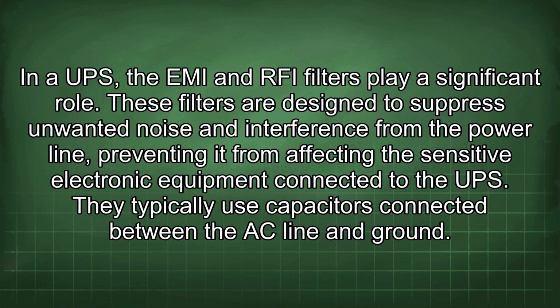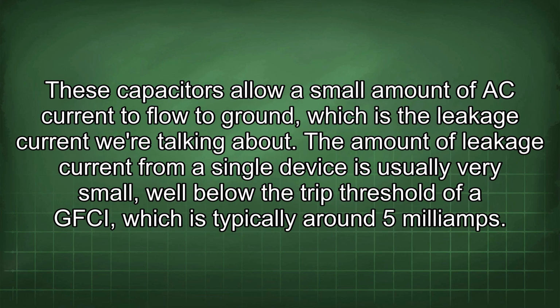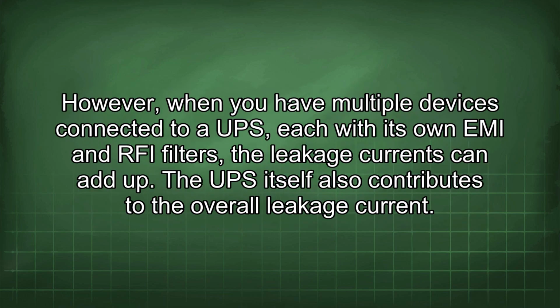They typically use capacitors connected between the AC line and ground. These capacitors allow a small amount of AC current to flow to ground, which is the leakage current we're talking about. The amount of leakage current from a single device is usually very small, well below the trip threshold of a GFCI, which is typically around 5 milliamps. However, when you have multiple devices connected to a UPS, each with its own EMI and RFI filters, the leakage currents can add up.